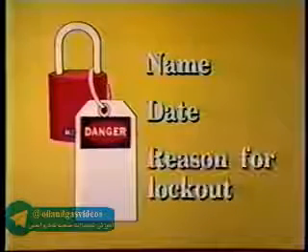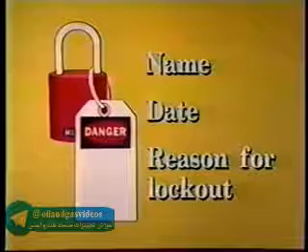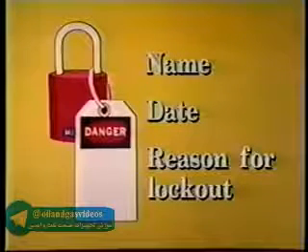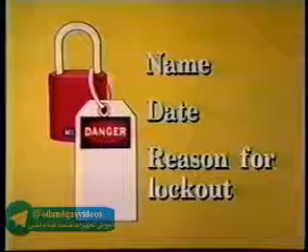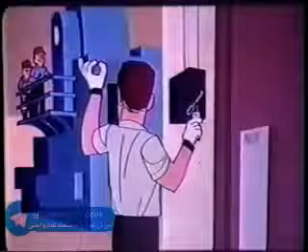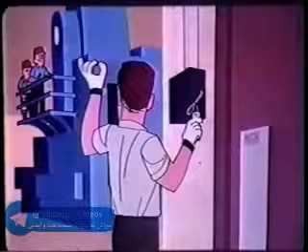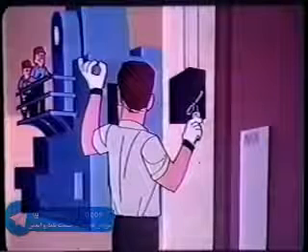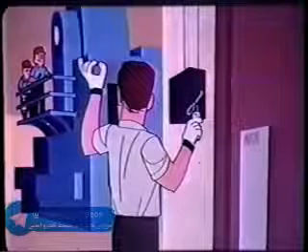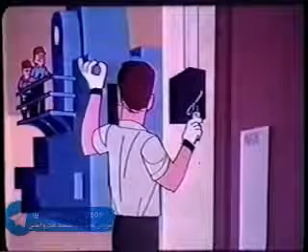Lockout programs require an identification tag to be used with the lock. The tag must indicate the name, date, and reason for the lockout. The tag shall be durable, able to withstand environment and exposure, and standardized throughout the workplace. Locks and tags shall be used together. The implementation of a lockout or tagout system shall be performed only by authorized employees. Affected employees need to be notified that a machine is or will be shut down.